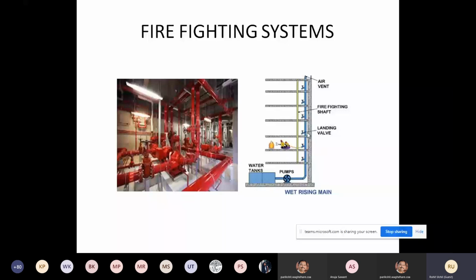or occupiers of the building, because you need to be trained to use the water which is coming out of these landing valves. They are at a very high pressure and at a very high discharge. So if an untrained person tries to connect a hose and open the valve and fight a fire, he might most likely get injured because he might not be able to handle the pressure.